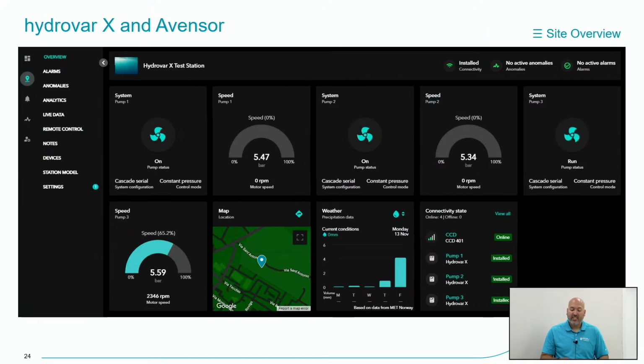Here would be the main dashboard of the live data. So if you didn't want to necessarily just look at the historical trends or data that's happened, and you just want to see what is specifically happening right now, you would go to the live data tab. You can see here we have a triplex Hydrovar X system going. There's 3 different pumps there. 2 of them are ready to go, but you'll see their speeds are 0. They're essentially in that standby mode. And then pump number 3 is running, and you can see the speed and pressure at which it's running.